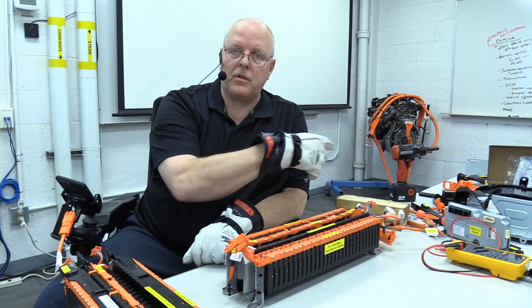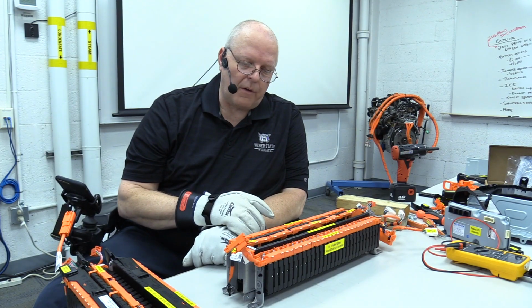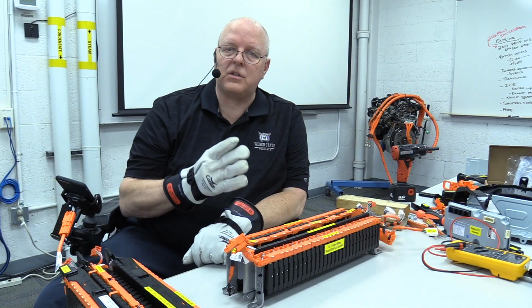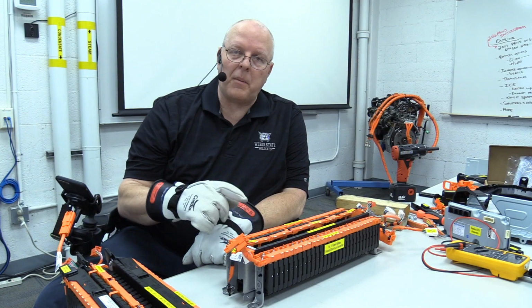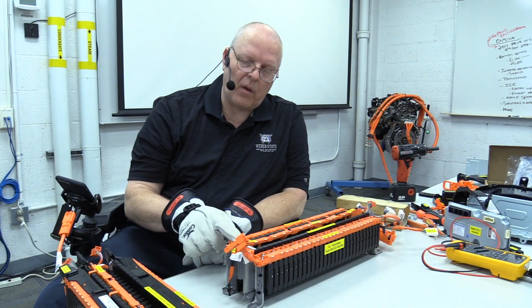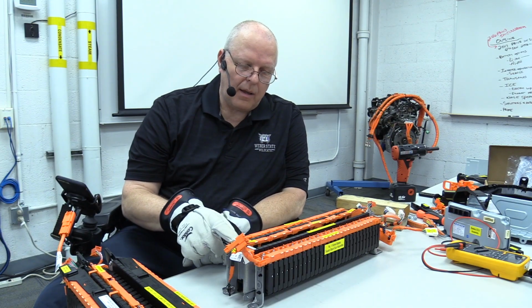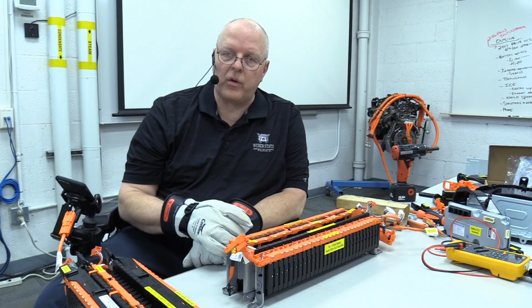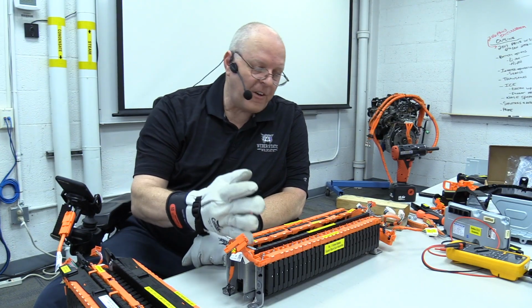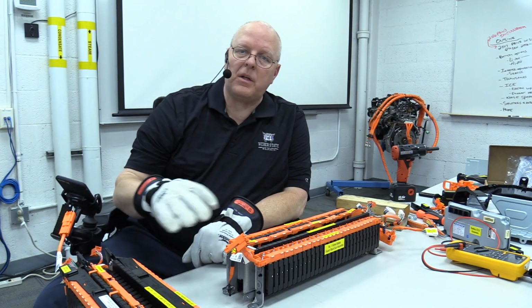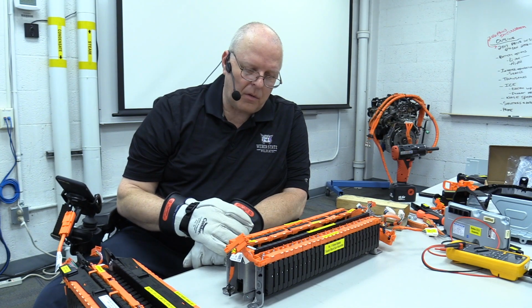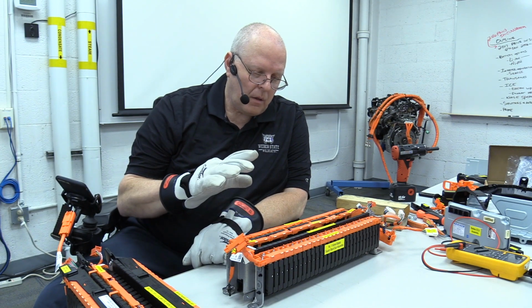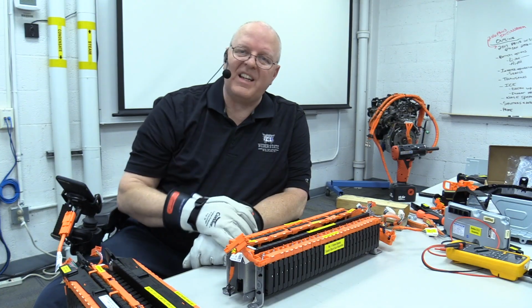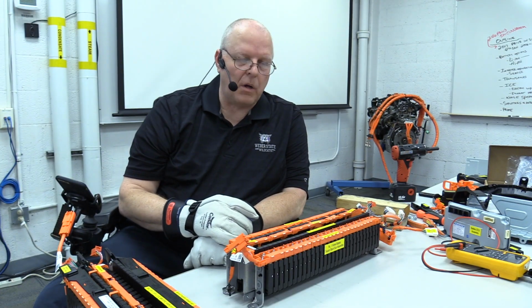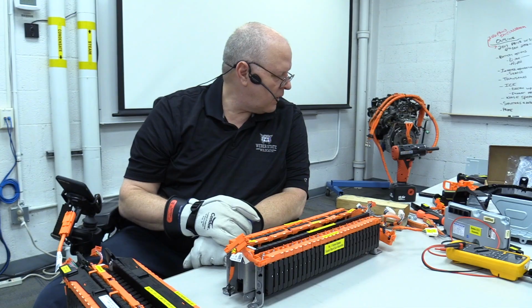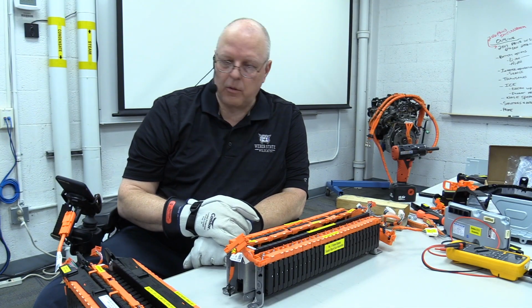They're all in series with each other. And so eventually, if the internal resistance gets too high, it'll become out of balance. It'll have the wrong voltage on the battery and will eventually trigger a trouble code. Of course, there are 56 battery cells combined between these two, and there would be trouble codes for each individual one. So a whole bunch of data and a whole bunch of trouble codes available there.